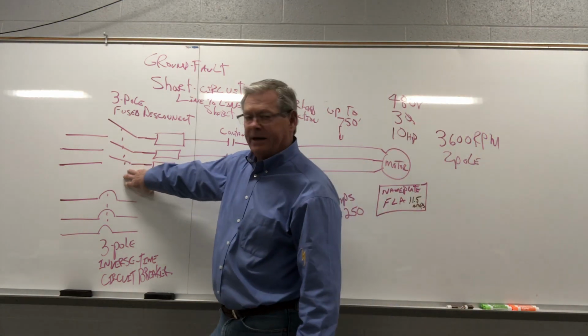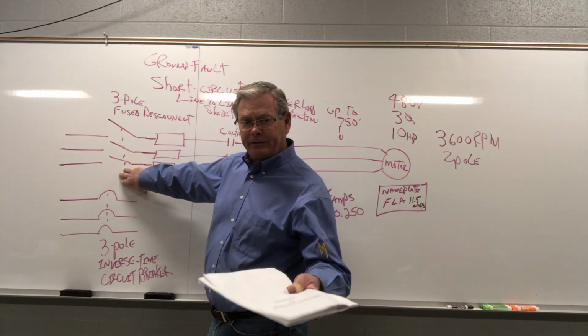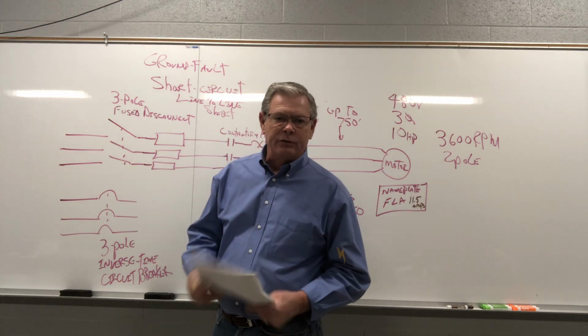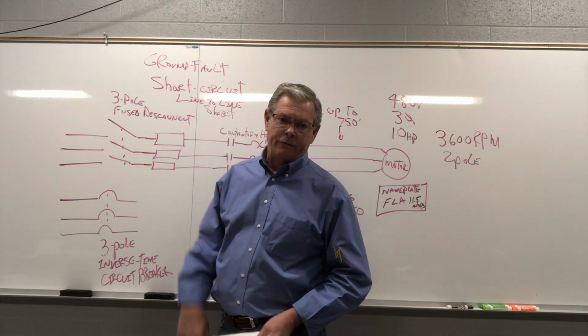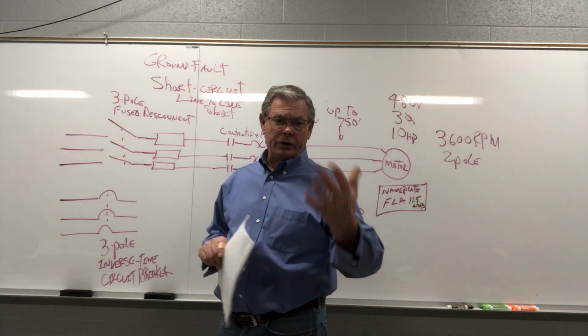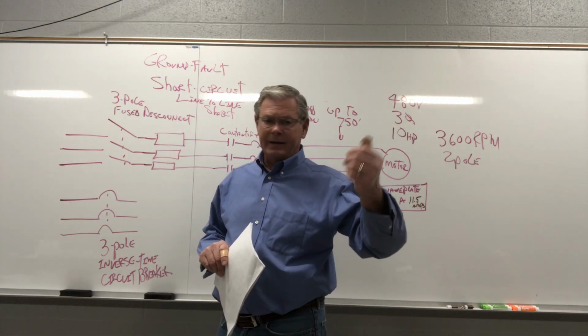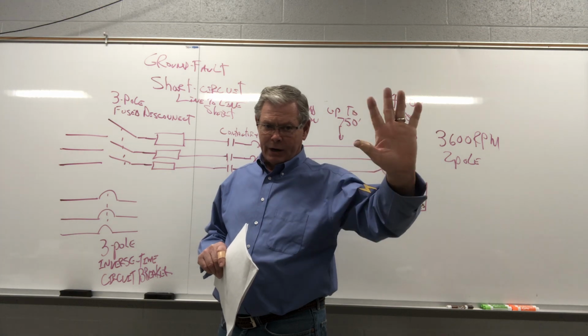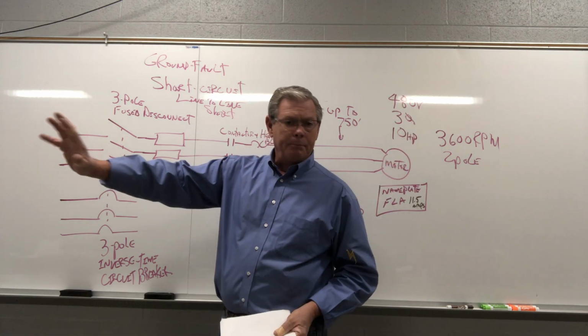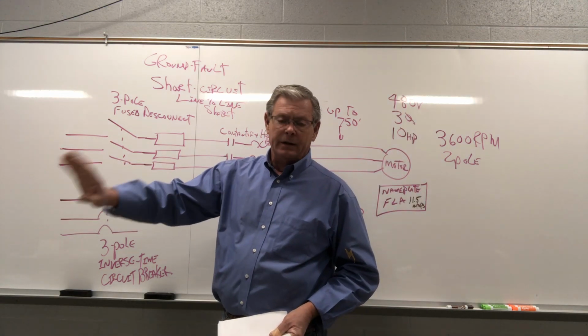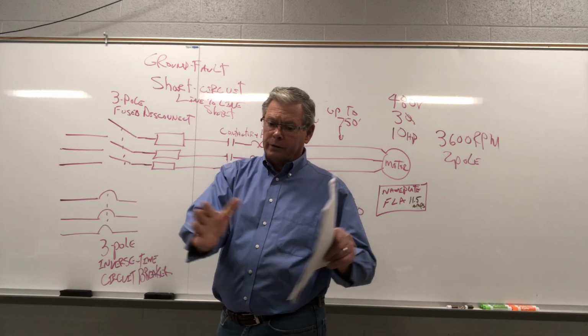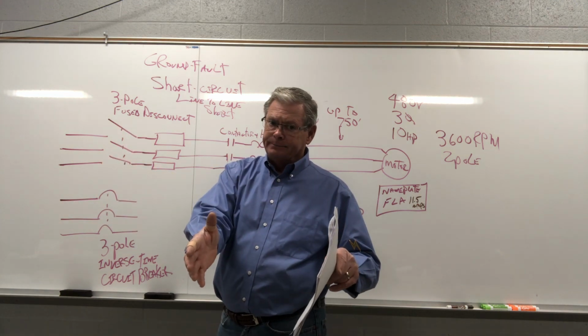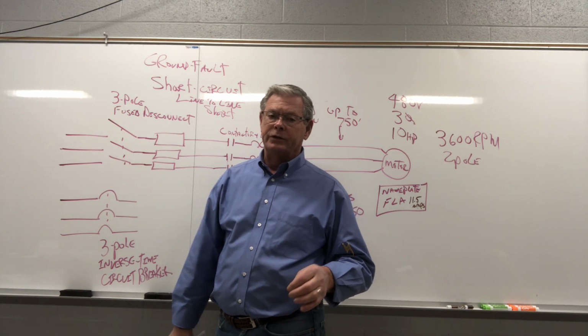We're starting over here, okay? This is where our three-phase comes in. The NEC says we must have a way to disconnect the motor from the main supply. So you're going to have in a motor control center an 800 amp breaker that's going to feed a bunch of motors. And each one of those motor starters is called a bucket. It's what they're in, in a motor control center.